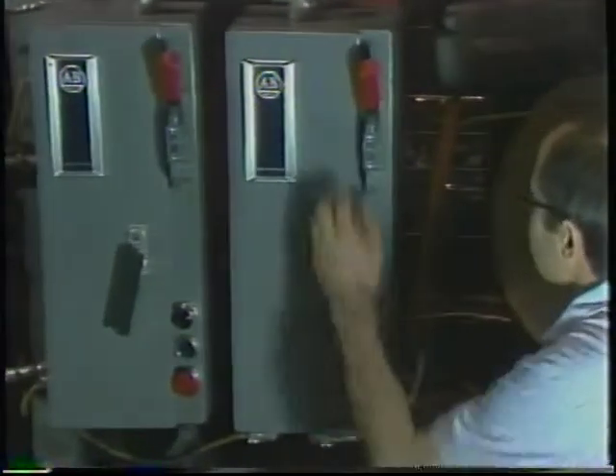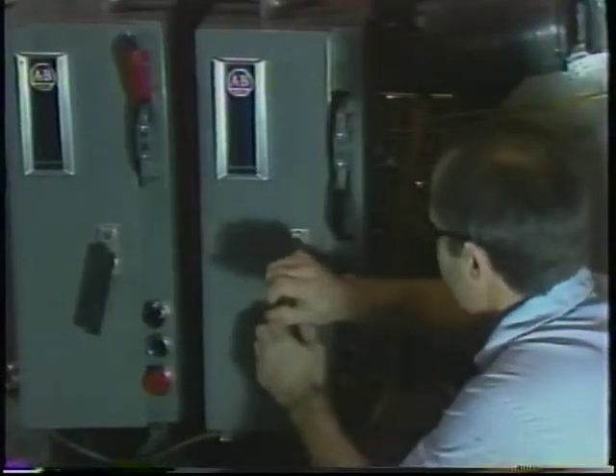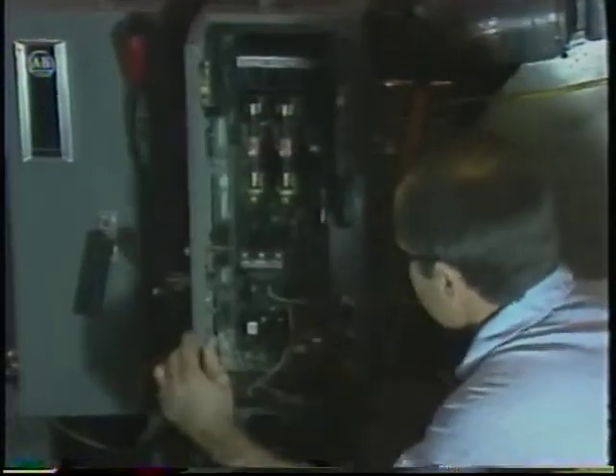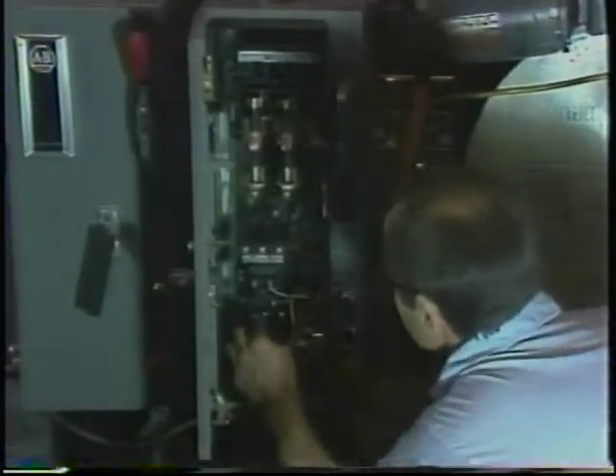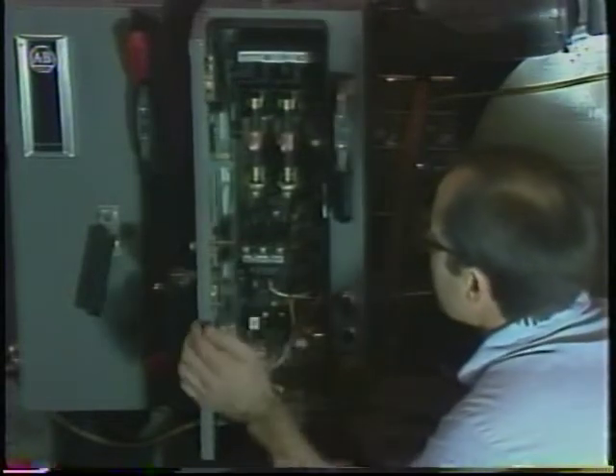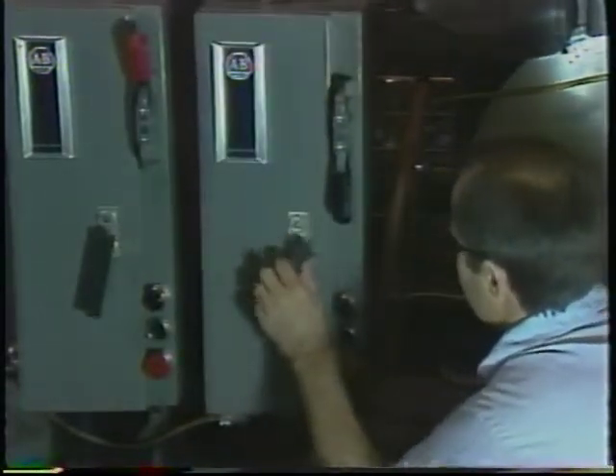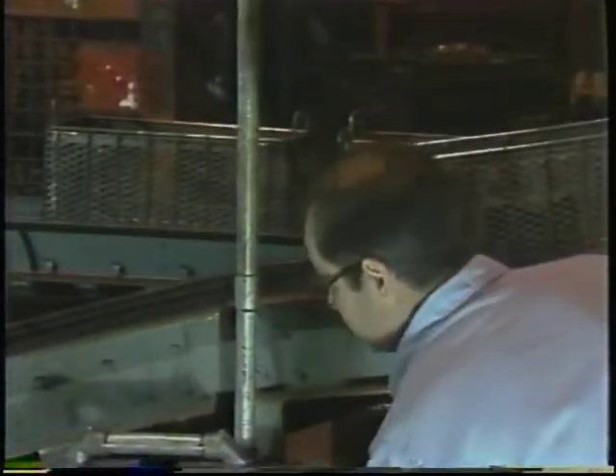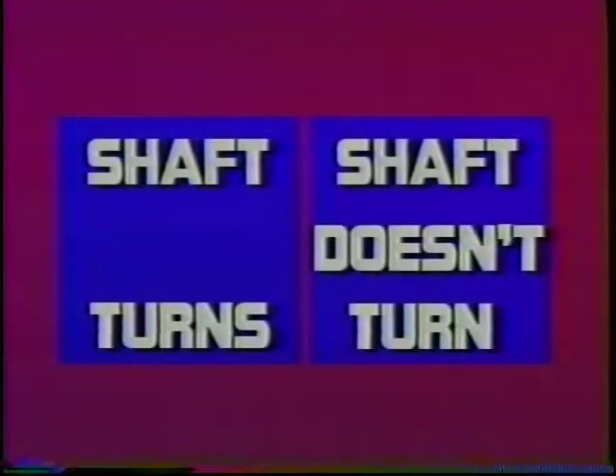When you do, you'll have a useful opportunity to investigate the symptoms further, analyze them, and perhaps save yourself some time and trouble. Make sure the machine is off and reset the overload breaker. Then, once you're sure it's safe, try to start the machine and be ready to observe closely. You will find one of two things happening. Either the motor will start up or the shaft will not turn at all. And in either case, you can analyze the situation and eliminate some possibilities, depending on the type of motor involved.